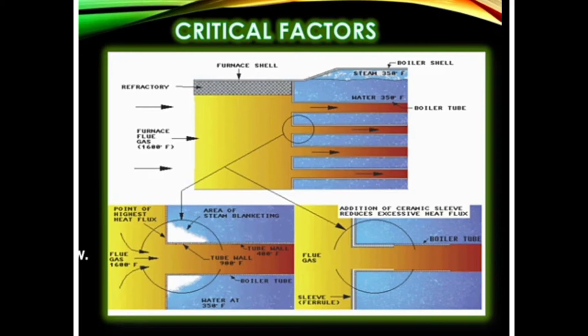We can reduce steam blanketing by using a ceramic sleeve, which reduces the excessive heat flux and prevents the steam blanketing phenomenon that causes failure of the boiler tubes.